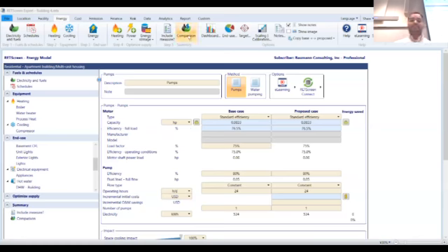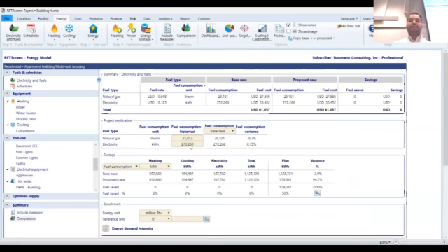So we go into the comparison tab, and this is a place where we mention the annual usage for the property. We determined that back in 2022 as the baseline case for us. The building had almost 31,000 therms of natural gas consumption and 270,000 kilowatt hours of electricity consumption. So the model that we have prepared is almost within plus minus 10% of the actual usage. This helps us be confident that the model I prepared is very much in line with the actual usage in the building.